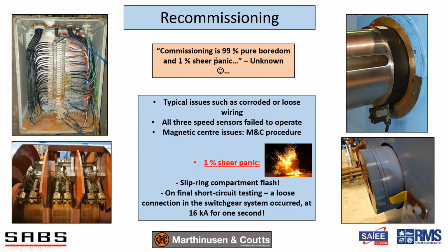We also had, those of you who have done commissioning or recommissioning, I always quote this, sometimes a little bit with trepidation, that commissioning is 99% pure boredom and 1% sheer panic. I don't know who said it, but I've heard it a few times. So we had the boredom stuff like corroded or loose wiring. When we first started up the drivetrains, none of the 3 speed sensors operated. And they're about 15 to 20 years old. Anyway, after 2 days, we managed to get all 3 working perfectly.